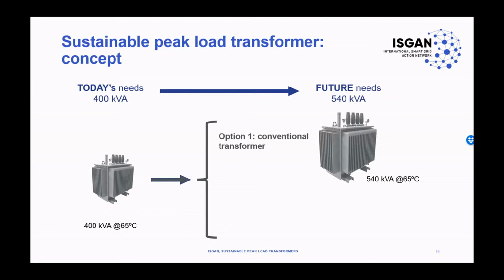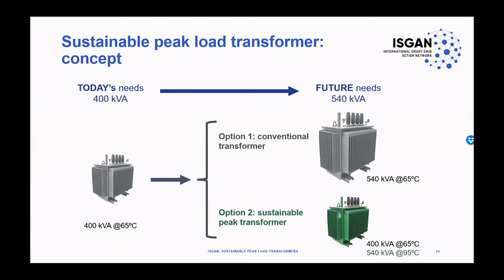The conventional option is to just exchange this transformer for a 540 kVA one. Again, this limit is there because of the temperature rise, maximum temperature rise of 65 degrees Celsius in the windings. Now, the second option, and there we come to our subject of today, is to exchange it by a sustainable peak load transformer. This is sometimes also called a dual nameplate transformer because you could say it has two nameplate values. We avoided this name because there is confusion about whether you can have two nameplate values and what it exactly means, a nameplate value. So we prefer the name sustainable peak load transformer.